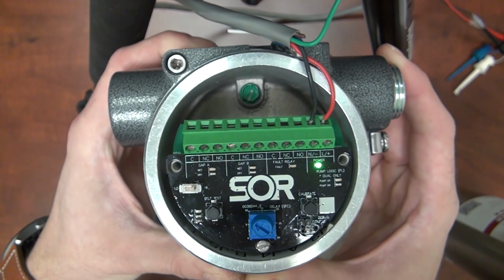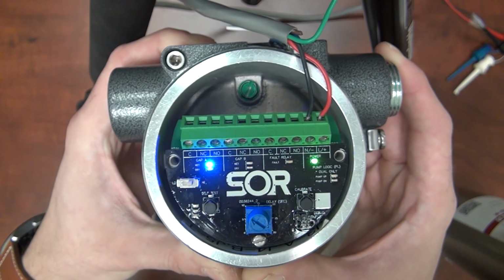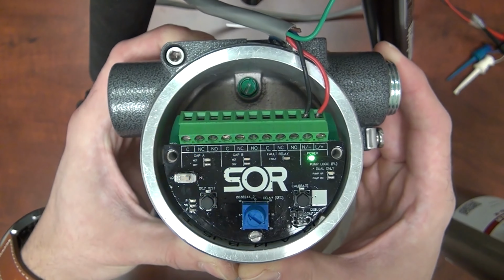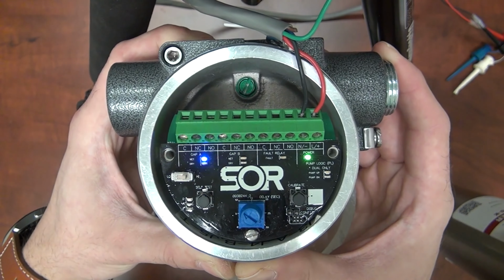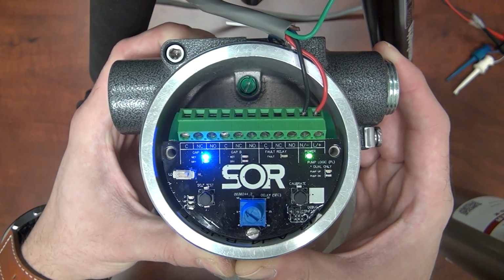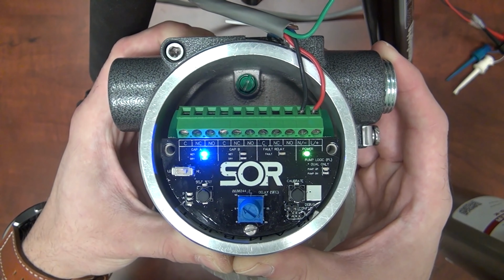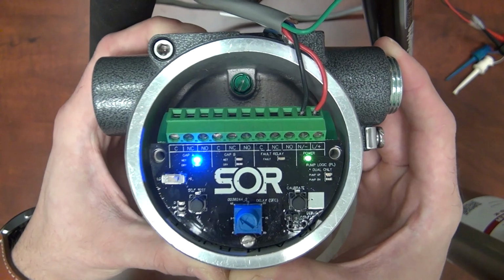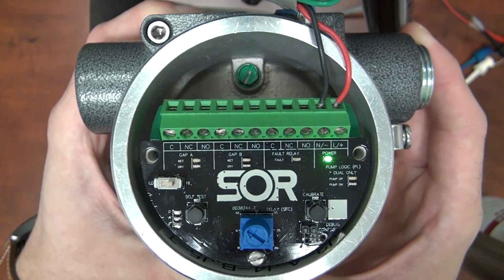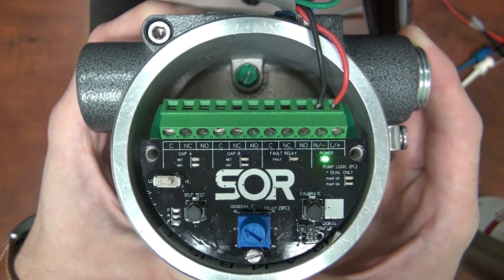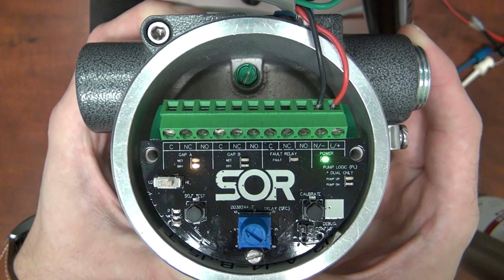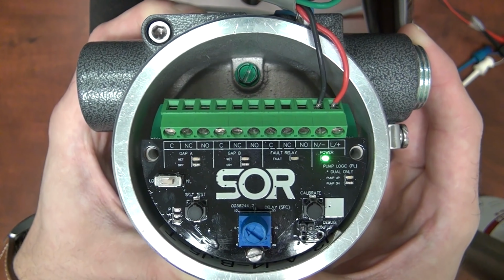Seen here, while the LED is flashing, the time delay is active. Once our time delay timer is finished, after about 10 seconds, the device will actuate and stay in the actuated state. The same can be seen when we remove it. The amber dry LED will begin flashing and remain flashing until the time delay is complete. At that point, it will deactuate.